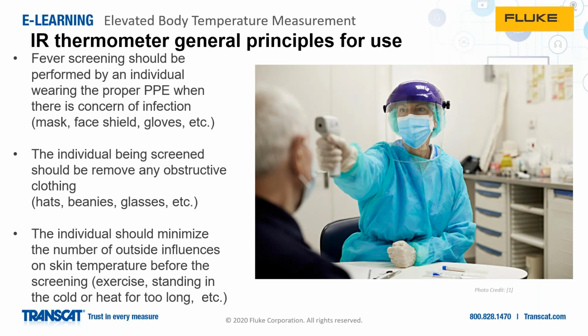But if you are using an IR thermometer for temperature screening, there are some general principles for use, especially during this COVID-19 pandemic. Fever screening should be performed by an individual wearing proper PPE when there's any concern of infection, like there is today. So this would include mask, face shield, gloves, etc. The individual who's being screened should remove any obstructive clothing from their forehead: hats, beanies, glasses, etc. And the individual should minimize the amount of outside influence on their skin temperature, whether that is exercise, or coming in from a very cold day in Minnesota or a very warm day in Arizona. Just anything where the skin temperature might be affected, trying to minimize that will result in a more accurate temperature reading.